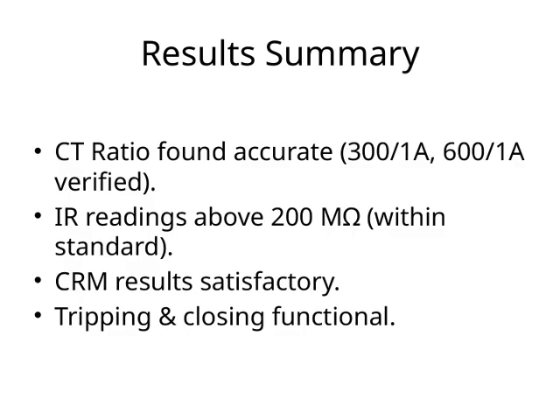Let's take a look at our results summary. First, the CT ratio measurements proved to be accurate, with the 300/1A and 600/1A readings confirmed through verification. This is important because it shows our equipment is functioning correctly and providing reliable data. Next, our insulation resistance readings were above 200 megaohms, which is well within the standard range. This indicates good insulation quality and suggests there's no immediate concern there.